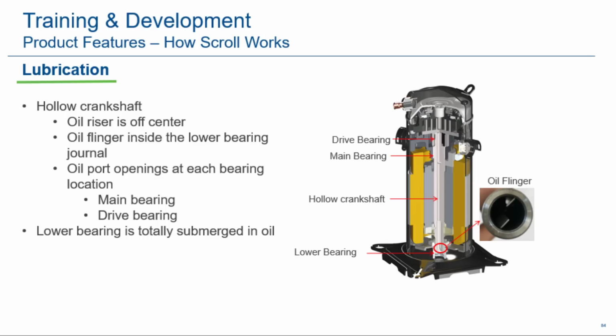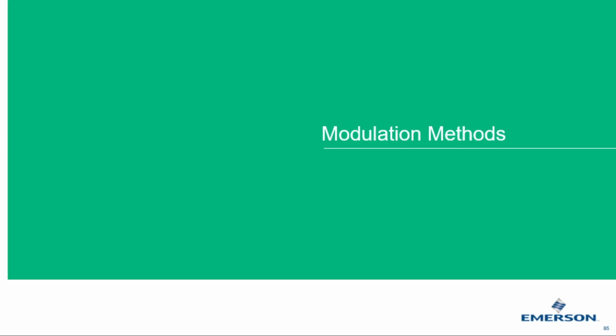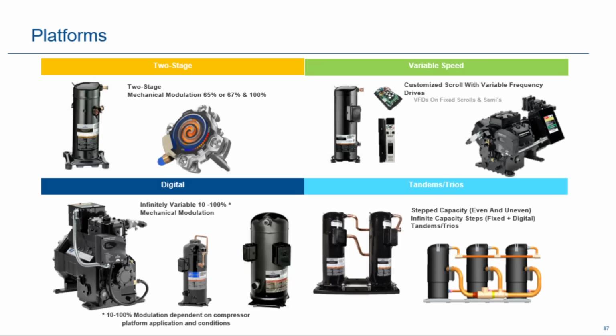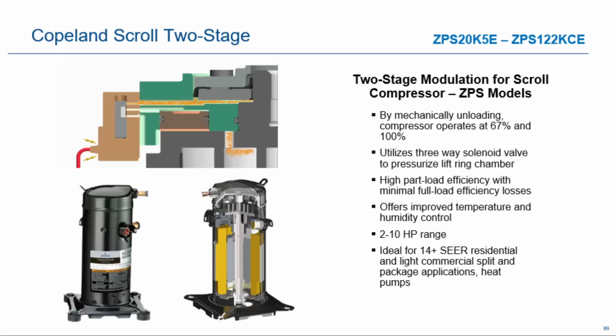Okay, modulation methods. There are quite a few different ones, and we're going to go through a few of them. We have two-stage modulation, variable speed, digital, and tandems and trios. So, two-stage scrolls. Basically, we've developed a scroll compressor that can do two stages. Inside it, there's a solenoid that will bypass gas. There are little bypass ports that will open up, so you can run compressors at 67 or 65%, depending on the compressor, up to 100%.